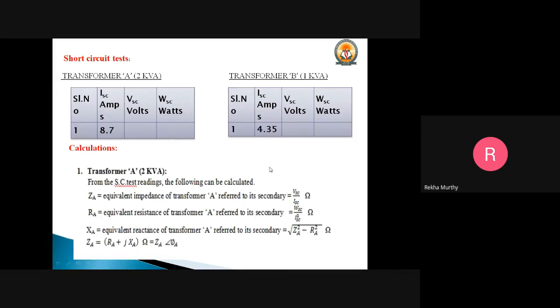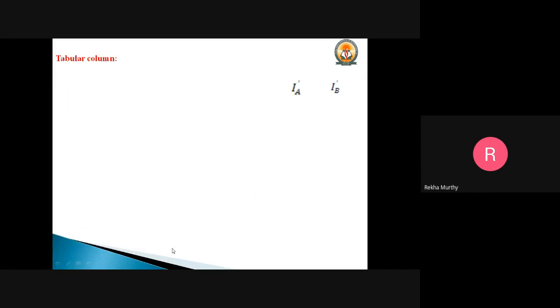Then the calculation we have to do is to get the respective values for transformer A. From the 2 kVA, we can get ZA, that is, as usual, VSC by ISC, and R, that is resistance, WSC by ISC square, so that we can find out the reactance. So it is square root of Z square minus R square. Then we can write ZA as nothing but RA plus j into XA in the rectangular form. And also it can be written in the polar form, that is ZA with an angle of psi A.